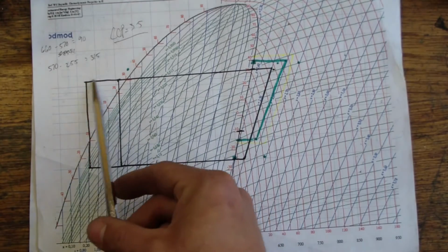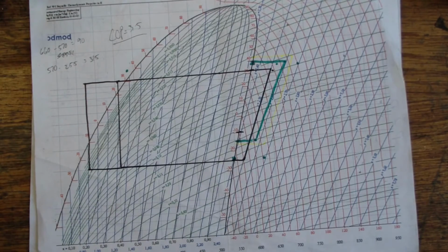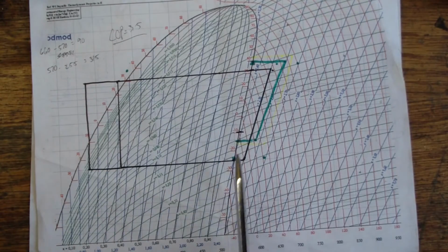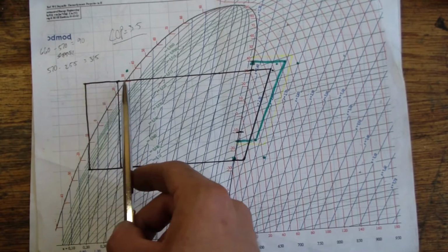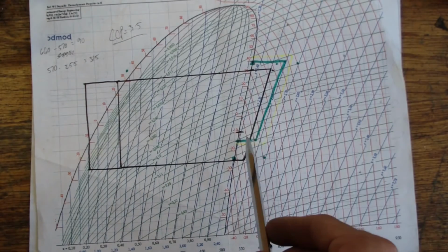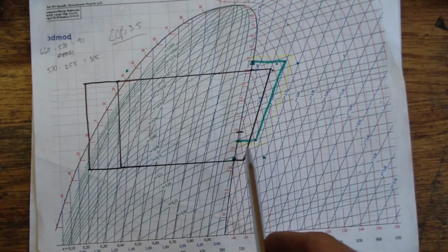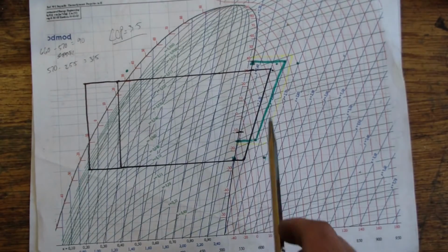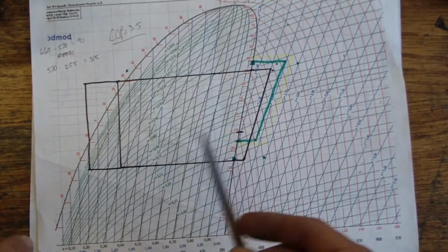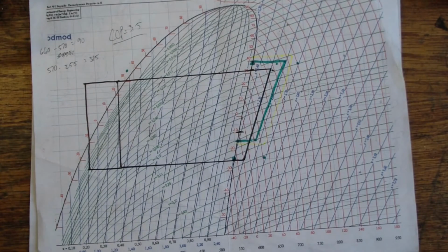Something seemed a little askew because it seems like I'm getting a lot more subcooling on this side than I am adding superheat on that side, and this is just based on the temperatures and pressures that I measured around the system. So some of these values might be a little bit askew, because you would assume if I'm discharging X amount of enthalpy on this side, that I would probably be adding that same amount of enthalpy on the other side. So I would expect those two to be more comparable, but anyway, I don't see that. It was kind of lighter, that green one and that yellow horn there, just the same machine running at probably slightly higher ambient conditions, slightly higher evaporator pressure and temperature. I don't remember what the conditions were of this. This was done some weeks ago, but I just pulled it out because I happen to have this diagram already listed up here. So what else can we discuss here?